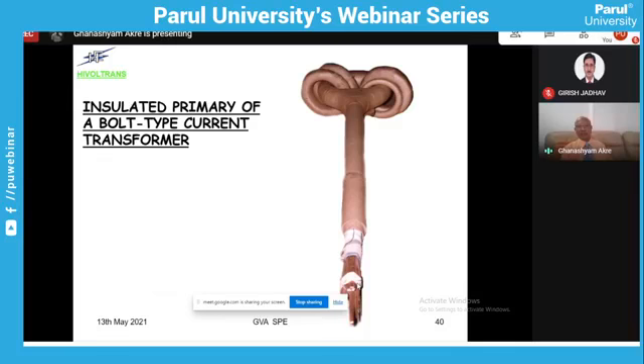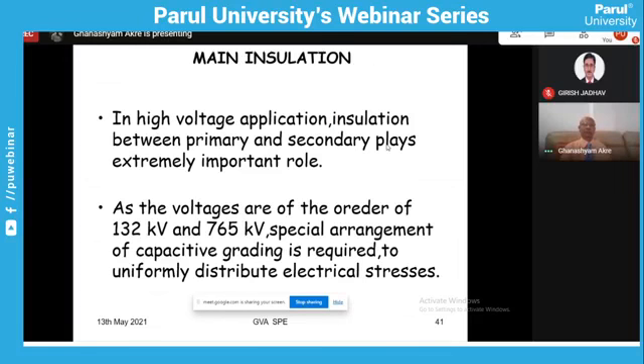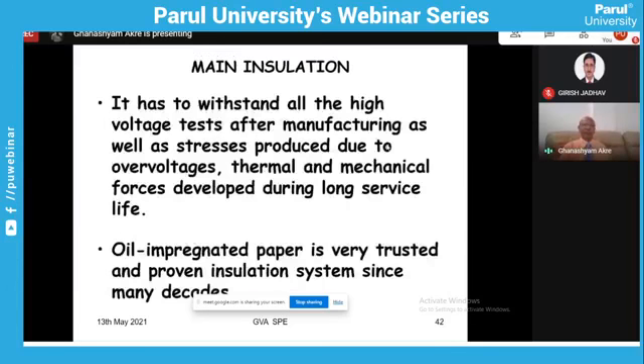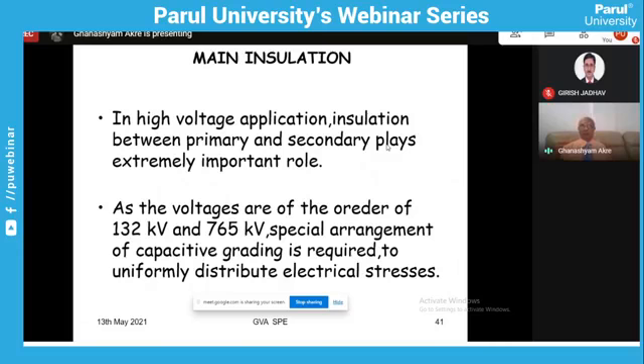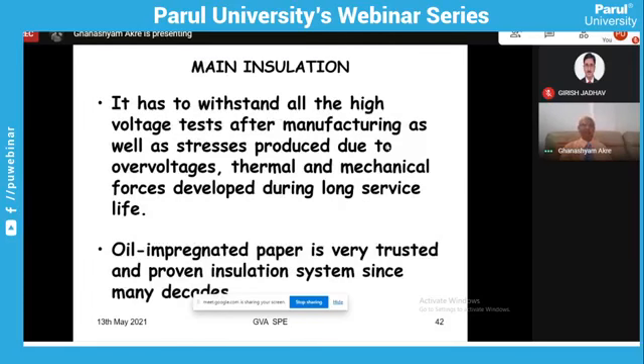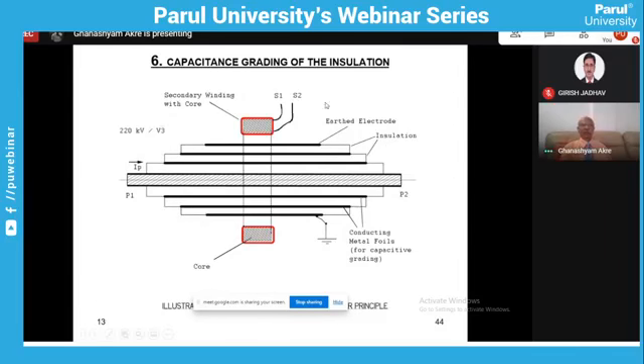Hence, this technology of high voltage insulation is very specific, and you have to adopt this principle of rounding. Here the insulation is not done simply by winding the paper, but this paper is also divided into sections of capacitances, which is called capacitive grading of the insulation. This is a subject in high voltage, and I will not take much time on it, but the insulation has to be very, very proper, and that is normally done in high voltage cases by providing capacitors. I will give an example in short of how this insulation is completed.